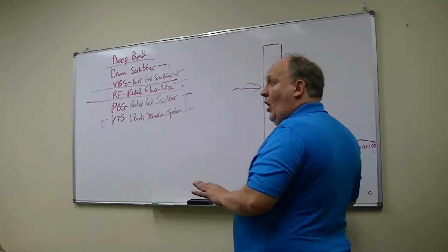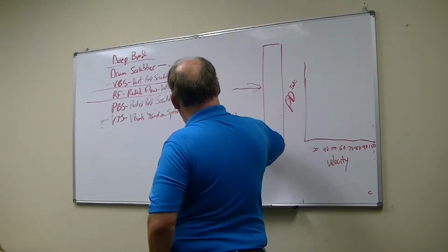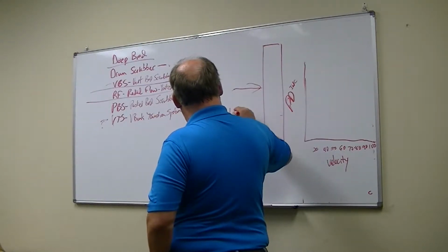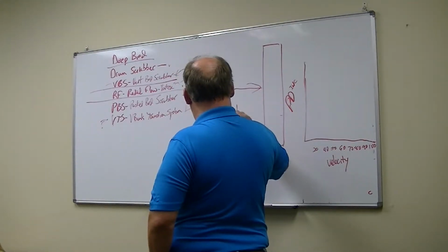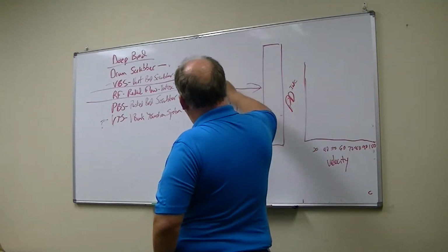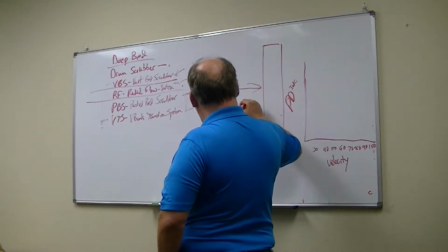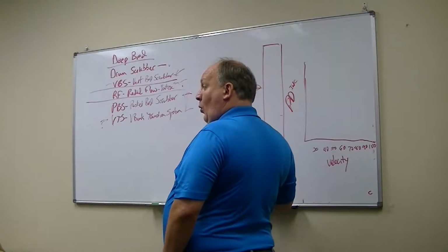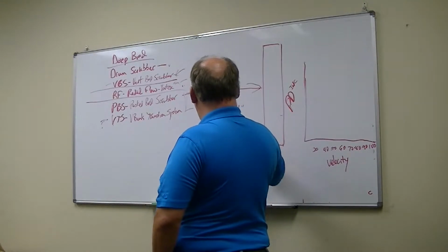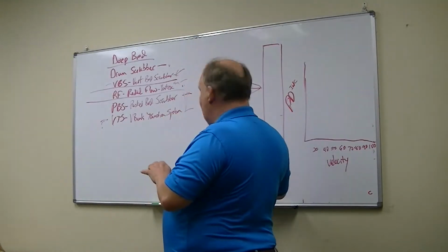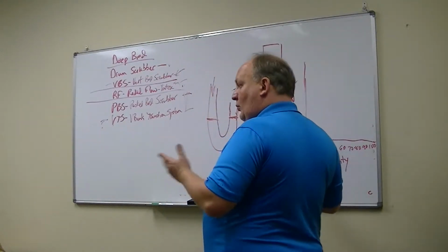So let's explain what inches of water column mean, right? If you have a tube here, and this tube has an elbow in it, and you fill this tube with water right here, okay, and then you blow air into here, the pressure that it takes to make this water go up 1 inch is referred to as 1 inch of water column, okay? All right, so it's sitting at equilibrium here, and then you blow into the end of it, and it goes up three inches. That's 3 inches of pressure, okay? We call that 3 inches.